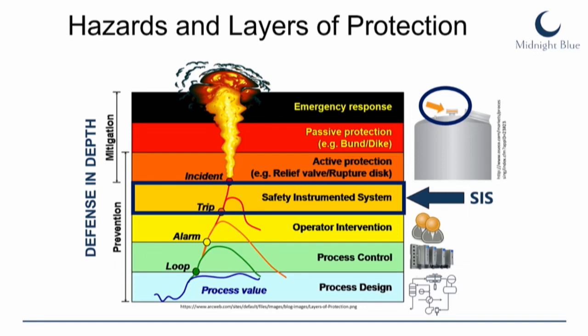There are layers of protection, starting with the design of the process. Then we have control loops. Then we have a human operator who reacts to the alarm. But as soon as the control system and human operator are no longer able to control the process safely, we have a so-called safety instrumented system — an independent control system which reacts to the hazardous condition and tries to prevent it. As you can see, this is the last line of defense before a hazardous accident happens.